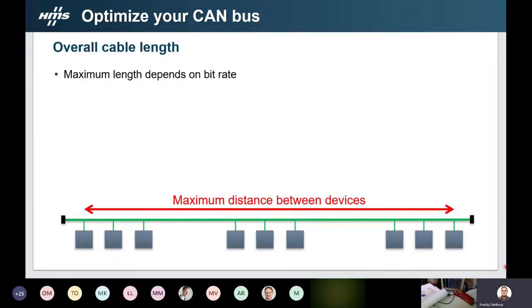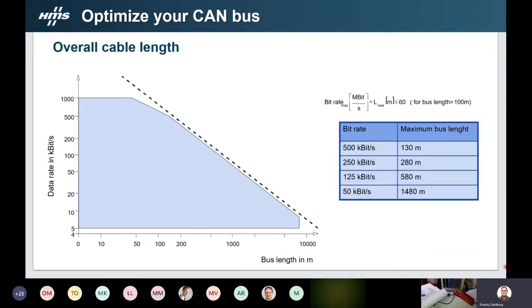So let's first talk a little more about cable length and maximum distance between devices. Basically, the longer distance you need, the lower speed you can use. You see here the speed and the length of the cable, and you have to stay inside this area. Here are some examples of the maximum cable length and which bit rate you can use.